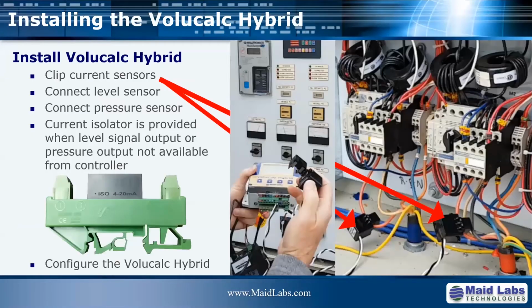So what was installed to get this? It's quite simple. We just installed one current clamp per pump to monitor when the pump starts and stops, and also to know what kind of current was drawn by the pumps, assuming all 3 phases are drawing about the same amount of current. To connect to the actual level sensor that was there, we're using a current isolator like what you see on the left hand side. So we basically piggyback on the actual level sensor that is there, and that's how the instrument is installed. As you can see, the instrument is very small. You can see it in my hand there with that very small current clamp. By the way, that size of current clamp is good for pumps up to about 50 horsepower because these clamps are good for 75 amps.